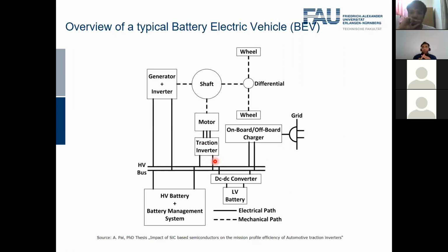The second question was about the insulation of the machine. As I mentioned today, the windings of the electrical motor restrict the maximum possible dV/dt permissible on the switches, meaning we cannot switch faster than, say, 15 kilovolts per microsecond, because we would end up damaging the insulation of the electrical motor. So this is not allowed.